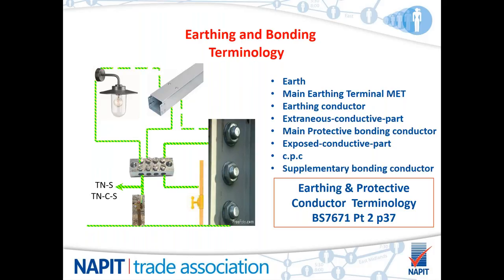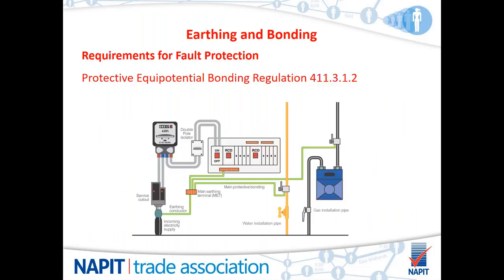And last but not least, we have the supplementary bonding conductors, commonly called cross bonding, but again put in place as a supplemental, that's why the word's there, to make sure that the potential of all of these pieces of equipment don't rise above the 0 volts of earth.